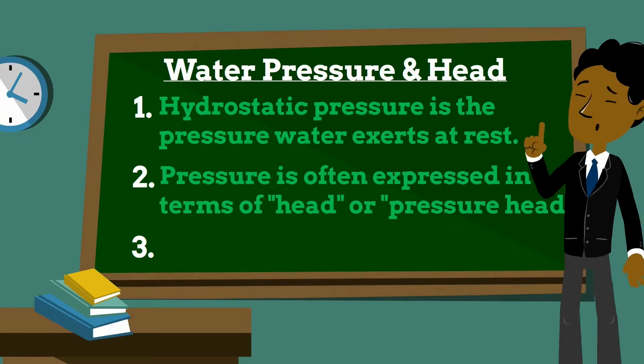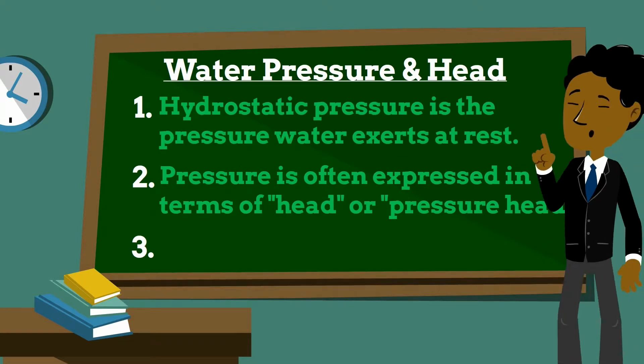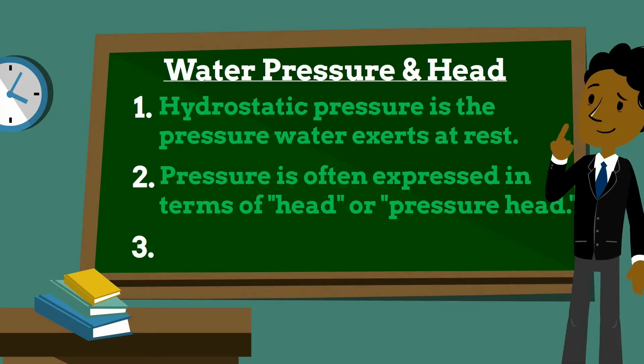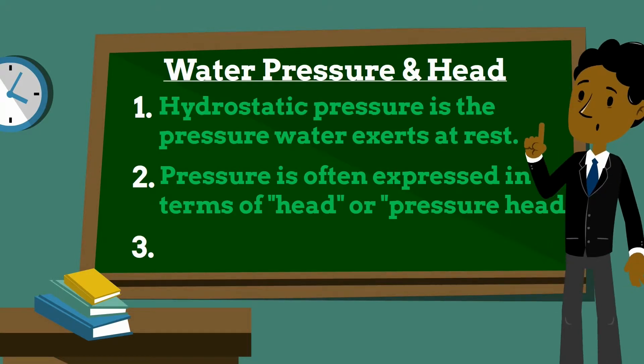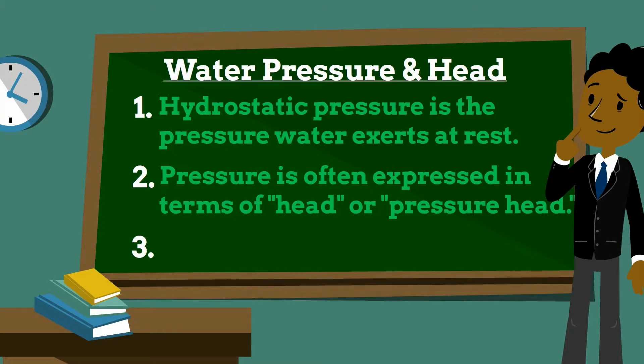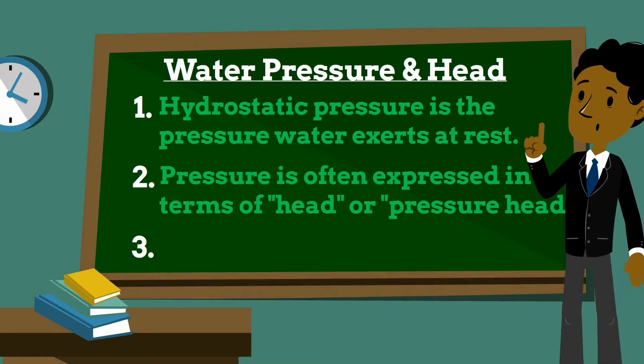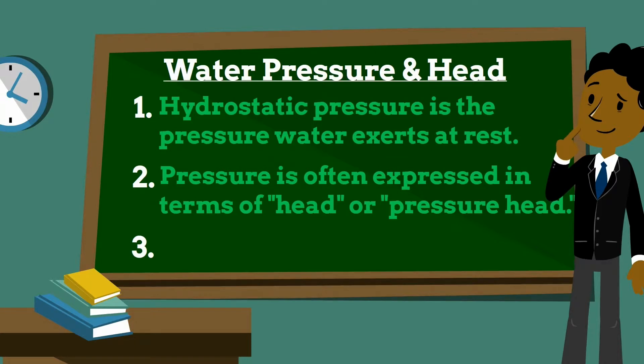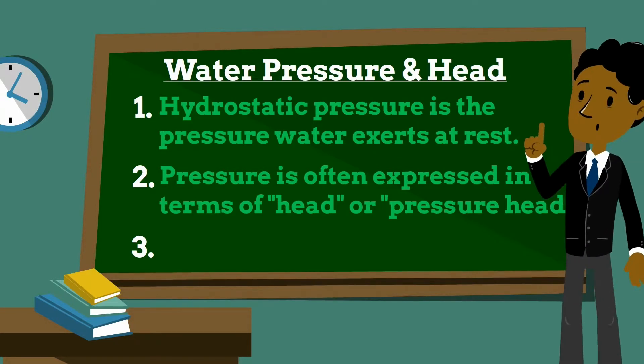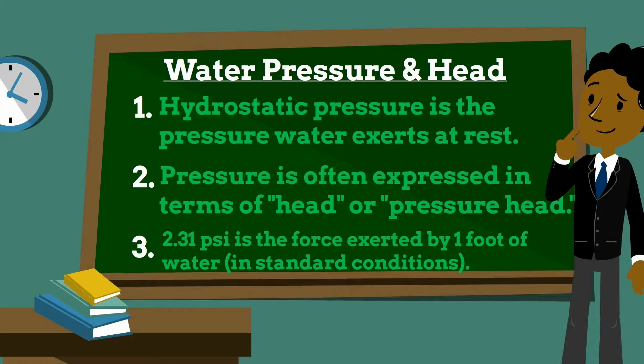It is often convenient to express pressure in terms of the height of a column of water, in meters or feet, instead of in terms of pounds per square inch. Pressure head, as it is called, is the actual or equivalent height of water above the point in question. A conversion you can use is that 2.31 PSI is exerted by one foot of water under standard conditions.